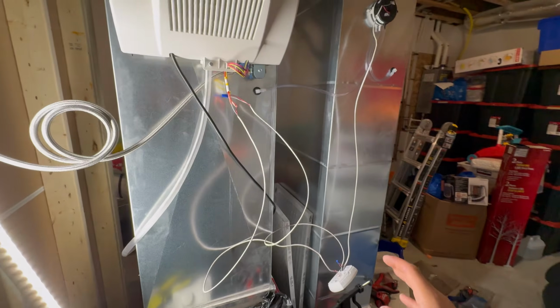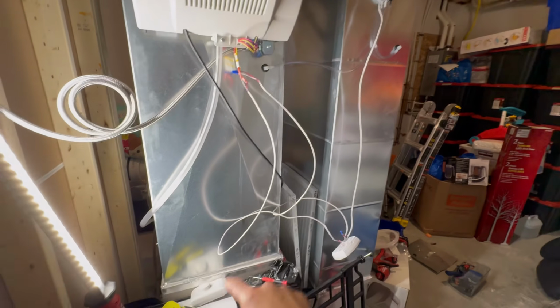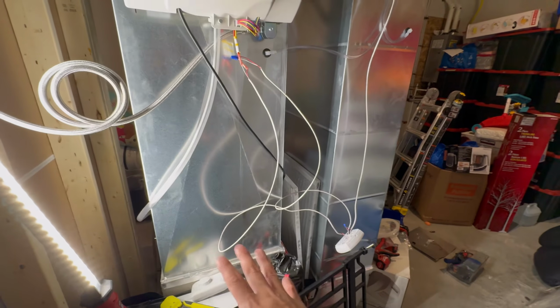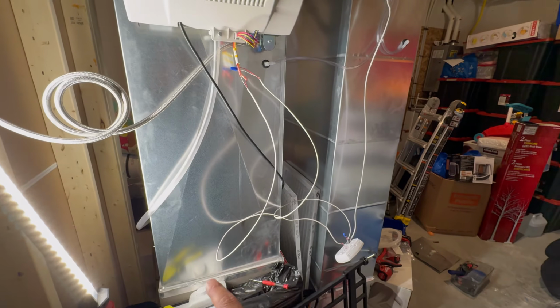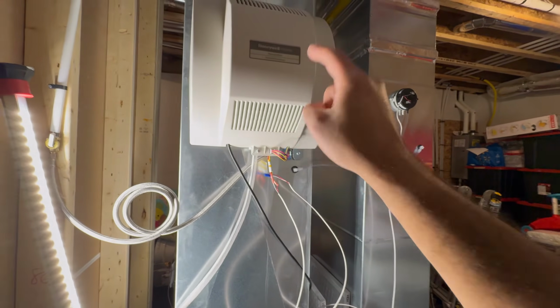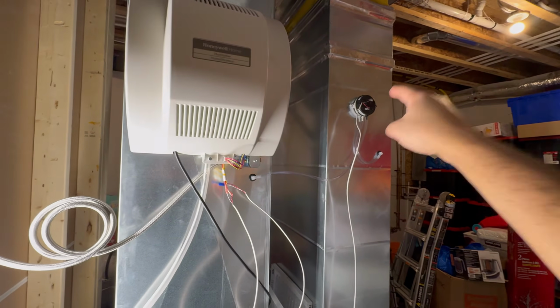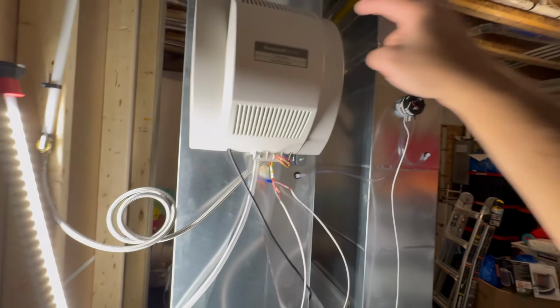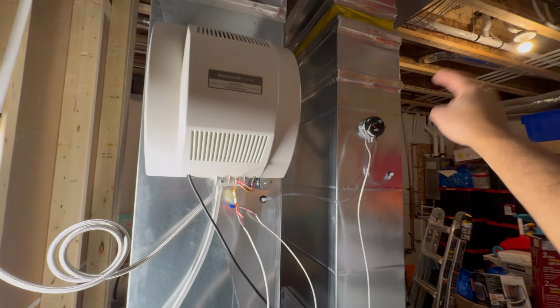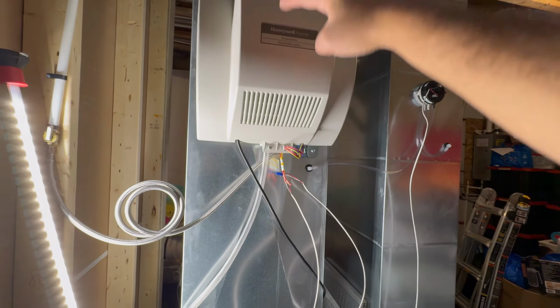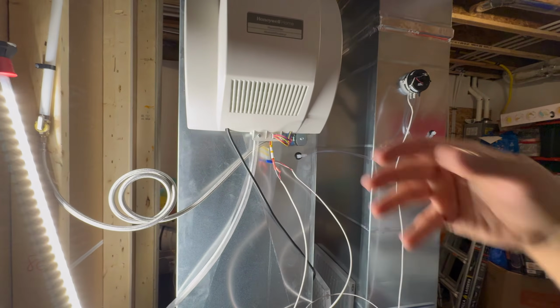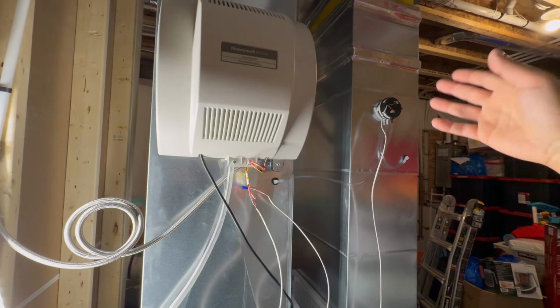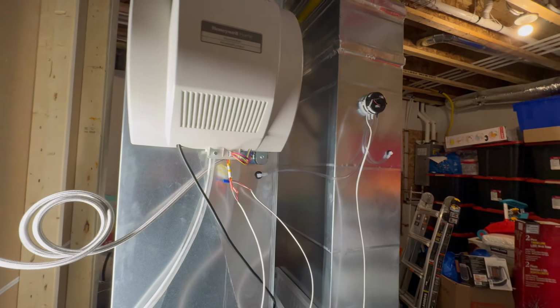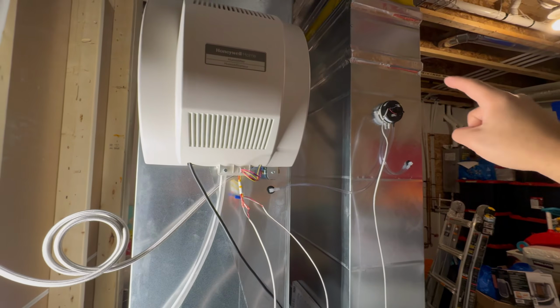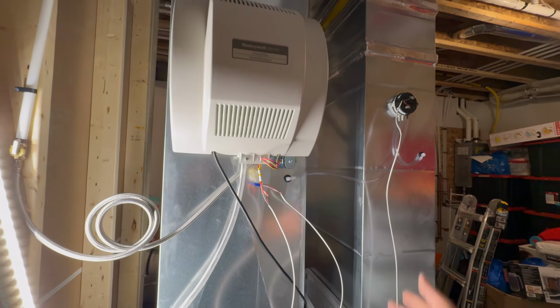So in both of these scenarios, whether you're using a digital thermostat or an analog thermostat, what's happening is the thermostat is calling for humidity. It's saying, hey, I need more humidity because I've dropped too low. But then, in order for this humidifier to kick in, that pressure switch has to say, yes, the furnace is now running, and now you should run the humidifier. Because if there wasn't a pressure switch, then the water would be going through the humidifier, but there's nothing happening. There's no air going through your home because the furnace isn't running. There's no air being blown into the house.